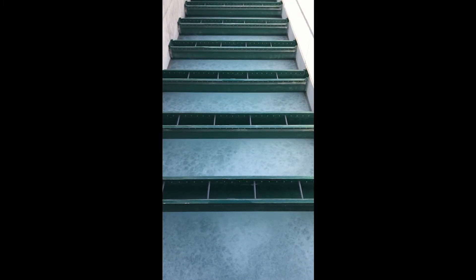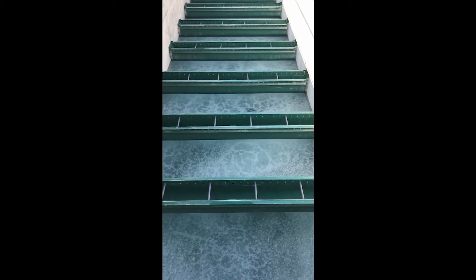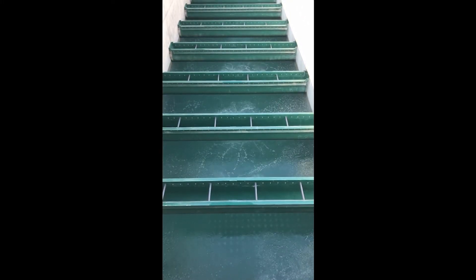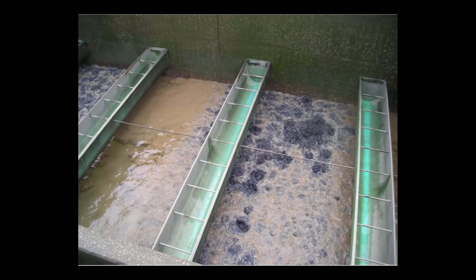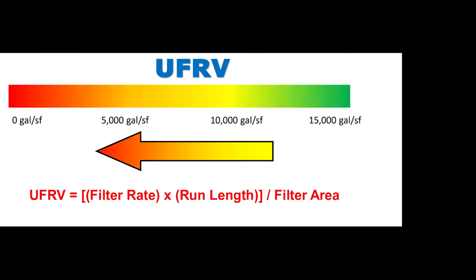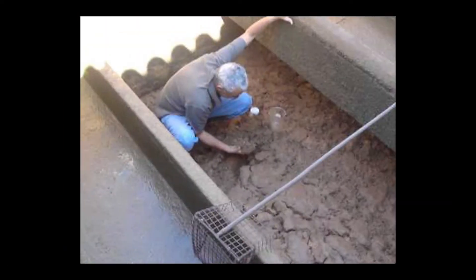Appropriate amounts of pressure drop or head loss through the nozzle at operating flow rate ranges is important to ensure proper distribution during backwash. Enough pressure drop through the under drain is required to overcome the head loss of the dirty media bed. Otherwise, uneven distribution occurs allowing unwanted channeling and poor media cleaning, which reduces subsequent filter run times and creates maintenance issues due to the leftover solids.